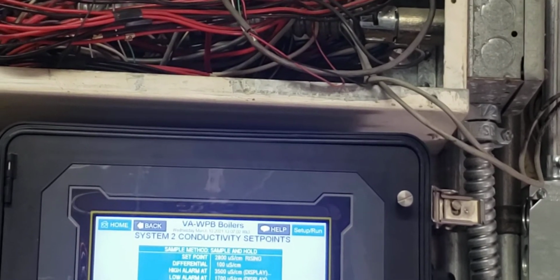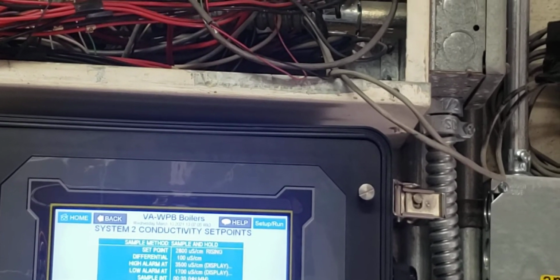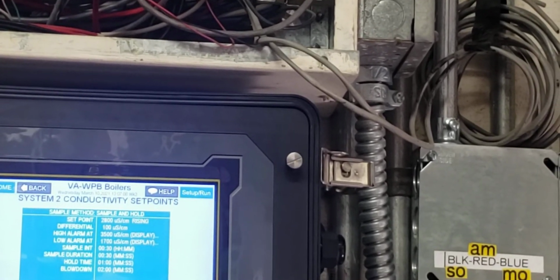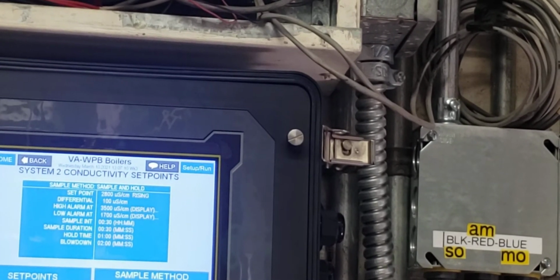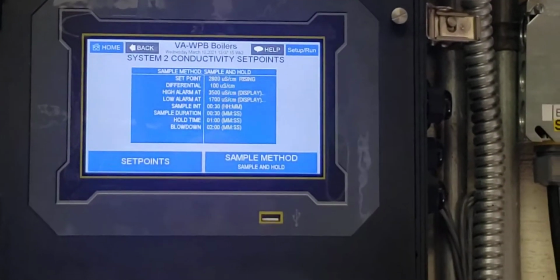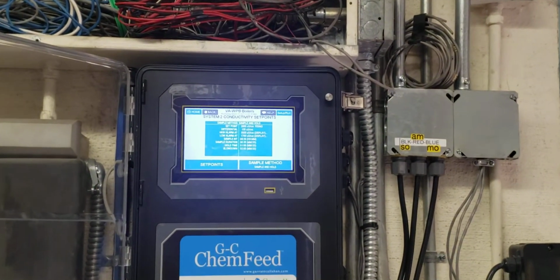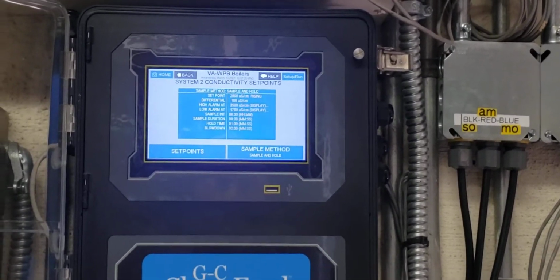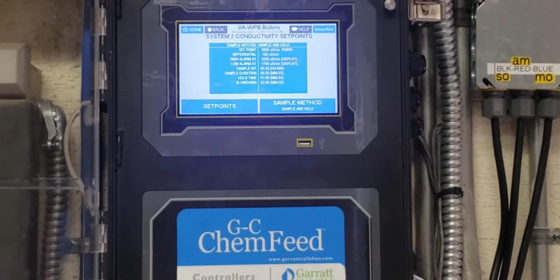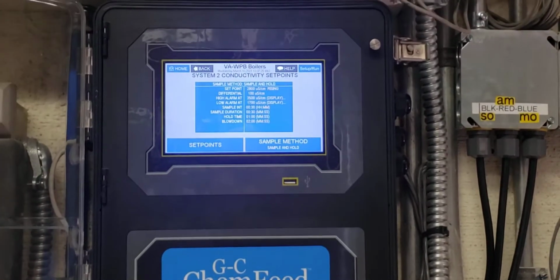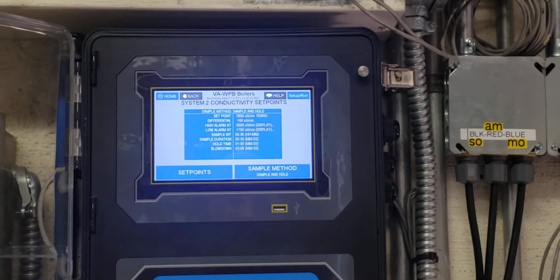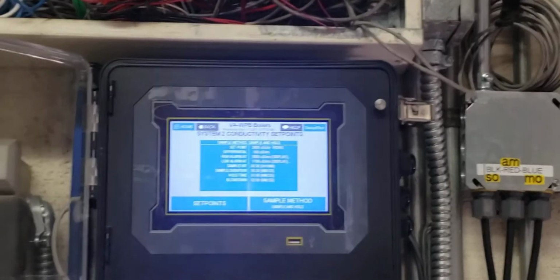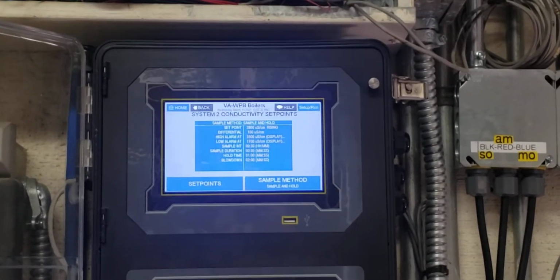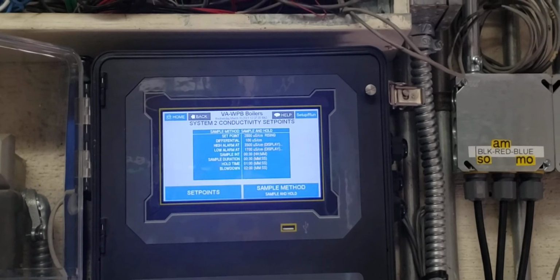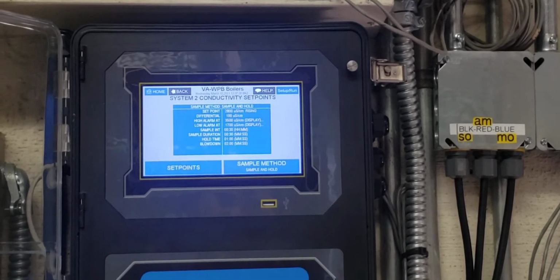That's not very long to blow down, though. I mean, if you have high conductivity, it's going to take longer than 2 minutes. Well, but it's twice an hour for 2 minutes straight. And remember, on boiler 1 there was a problem with the makeup water valve, so it was blowing down too fast, or too much. The valve wasn't opening, so he was manually filling boiler 1. I forget what was going on at that point in time. I think the softener might have been an issue too. Who knows if we would have caught that in time, when it was blocking all that and not feeding. Correct.